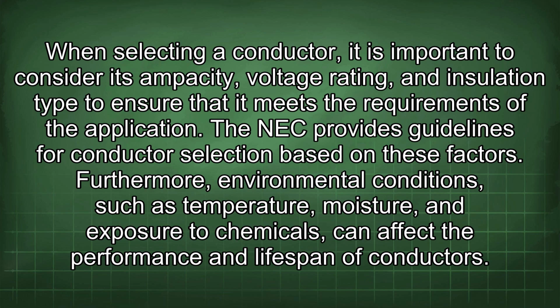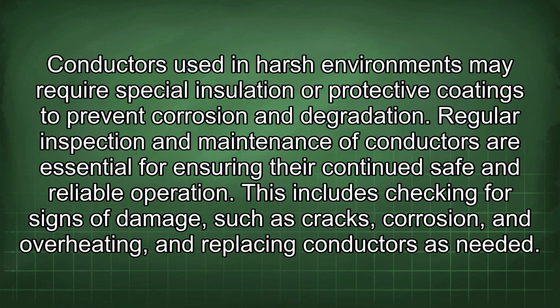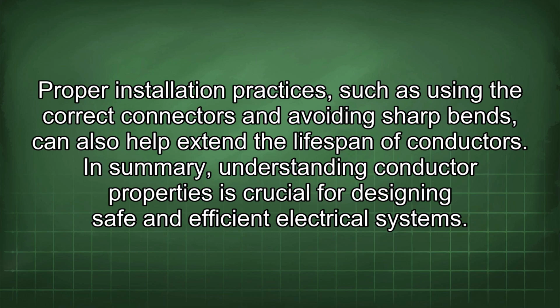Furthermore, environmental conditions such as temperature, moisture, and exposure to chemicals can affect the performance and lifespan of conductors. Conductors used in harsh environments may require special insulation or protective coatings to prevent corrosion and degradation. Regular inspection and maintenance of conductors are essential for ensuring their continued safe and reliable operation. This includes checking for signs of damage, such as cracks, corrosion, and overheating, and replacing conductors as needed. Proper installation practices, such as using the correct connectors and avoiding sharp bends, can also help extend the lifespan of conductors. In summary, understanding conductor properties is crucial for designing safe and efficient electrical systems.